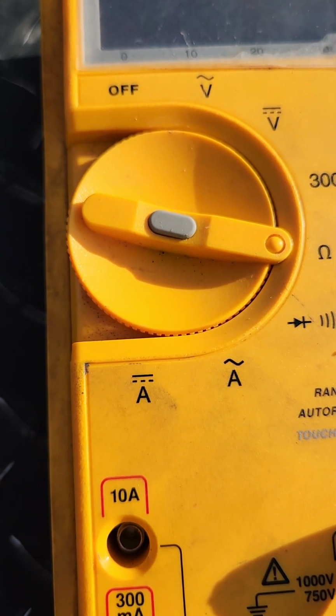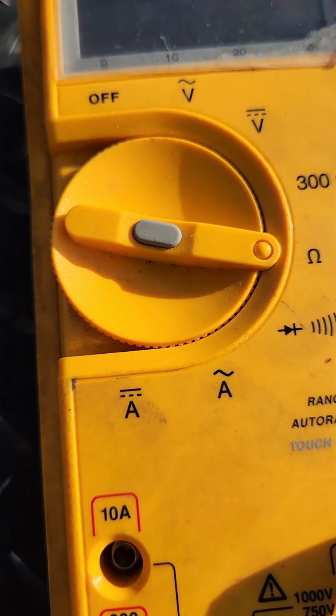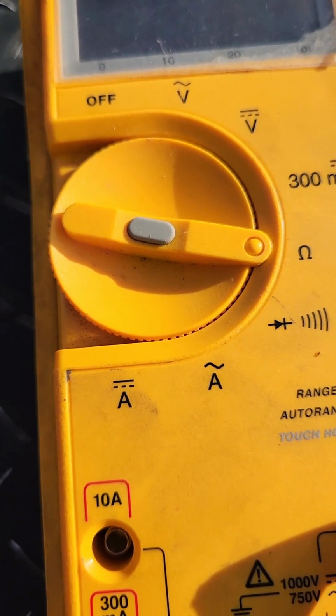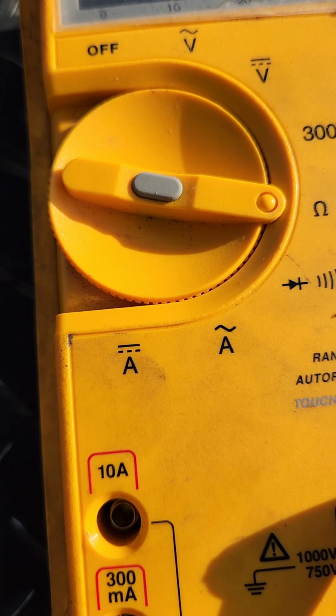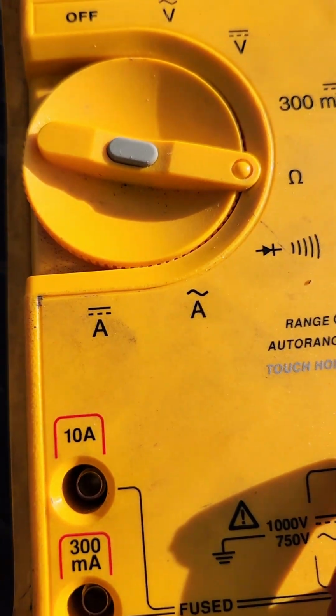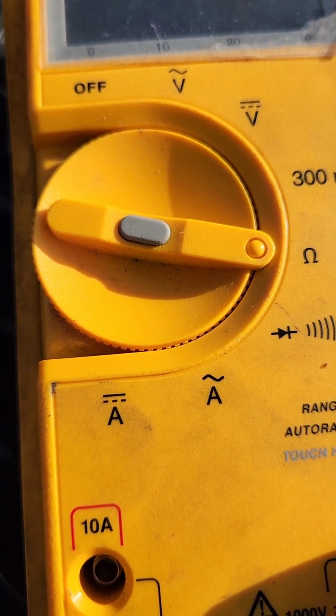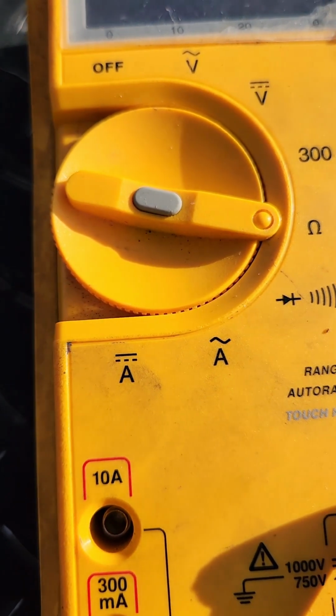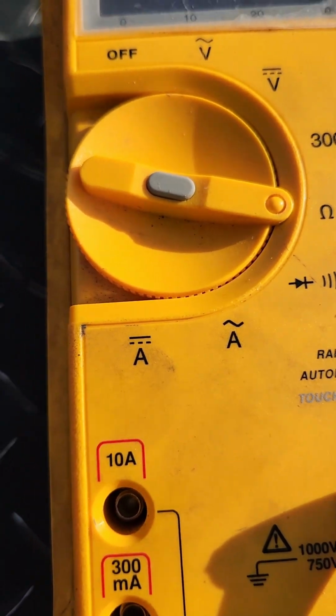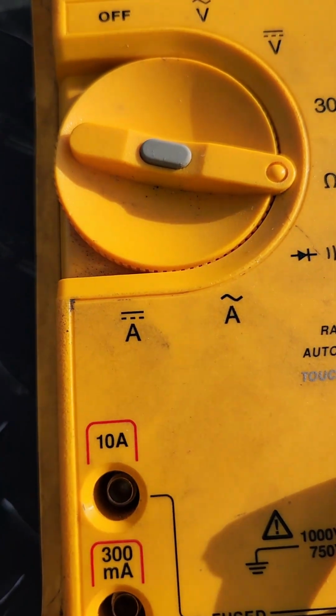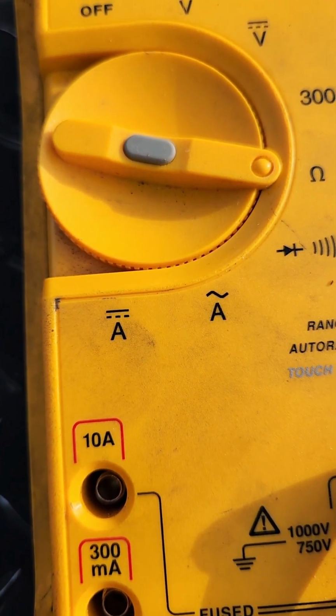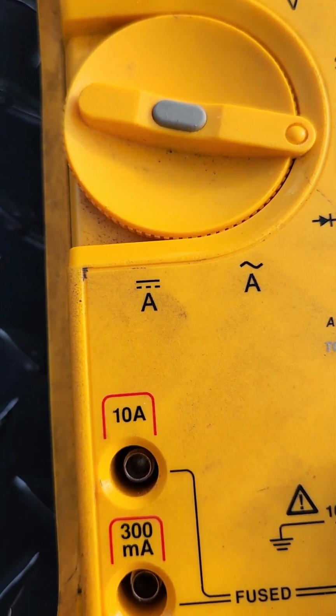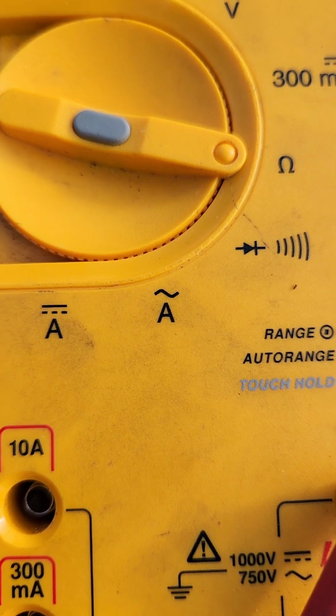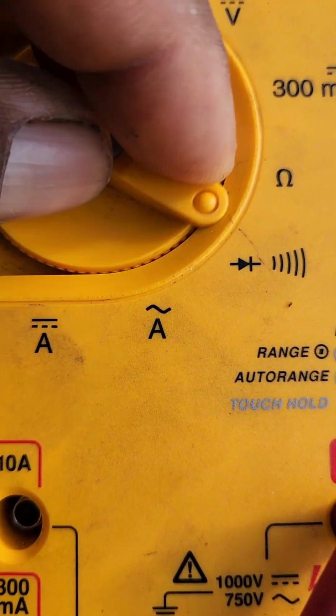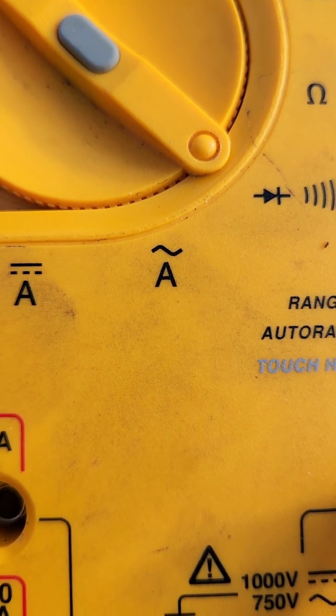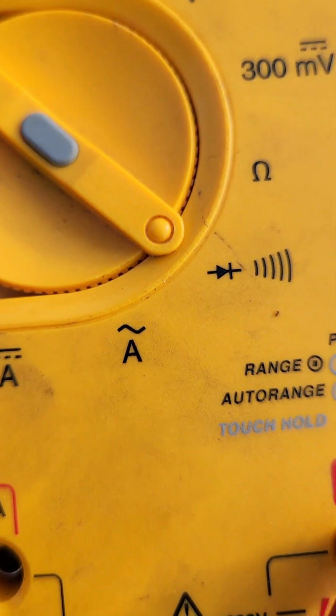All the machines these days, most especially the hydraulic ones, the big machines, have solenoids that pull up a spool and engage hydraulic flow. So coils are very common in cars and in machinery. On the side is usually marked how much resistance the coil has, usually from 5 to 30 ohms, depending on the manufacturer and how many coils it has. If you put a test meter on a straight piece of wire, normally you get 0 ohms. But after about 10,000 turns of wire, there's a lot more resistance because there's a lot more conductor. So this is for checking coils, wires, solenoids. And this one is for checking usually fuses. You can check your fuse with ohms too.